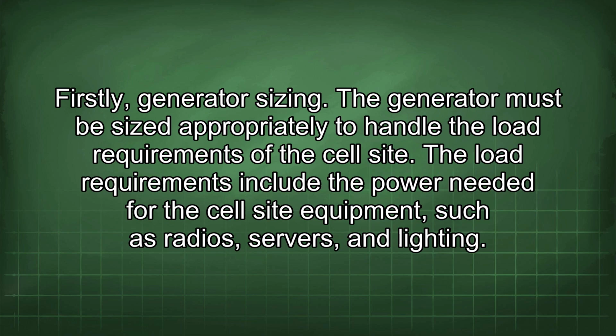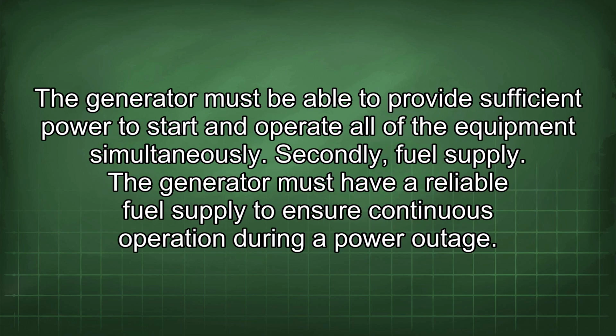Firstly, generator sizing. The generator must be sized appropriately to handle the load requirements of the cell site. The load requirements include the power needed for the cell site equipment, such as radios, servers, and lighting. The generator must be able to provide sufficient power to start and operate all of the equipment simultaneously.